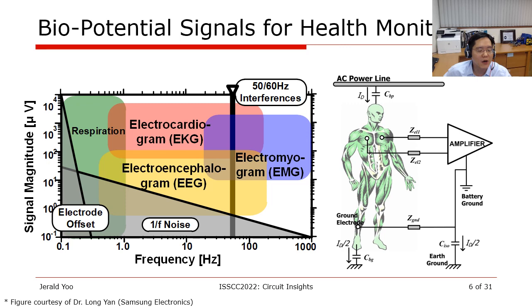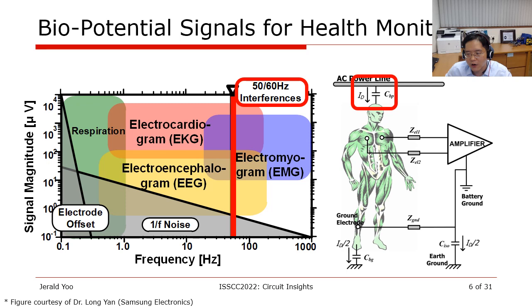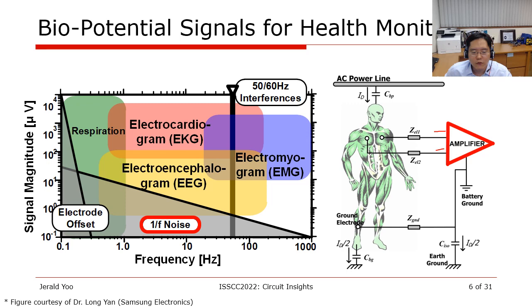One thing to note is that the electrode DC offset — meaning the DC level coming from the positive port and the negative port of the amplifier — will always be different, and that is reflected as an electrode offset. Also very important in biopotential are 50–60 Hz interferences. You cannot get away from them these days. They couple unnoticeably to your body and are reflected as a common mode to both positive and negative inputs of the amplifier. So the amplifier needs a really good CMRR to handle this. The amplifier also has 1/f noise, which unfortunately matches exactly with the signal band of interest, so the amplifier also has to deal with this noise.